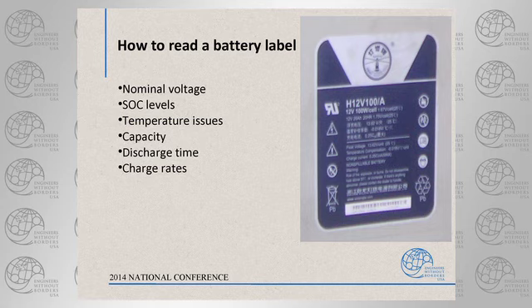Now some of them are only rated for 5 minutes, and you go, wait a second, the battery's only good for 5 minutes? Yeah, at that rate it's only good for 5 minutes. So capacity is always going to be at a given rate of hours, and if you go less than that rate of hours, you won't get the full capacity out of it.